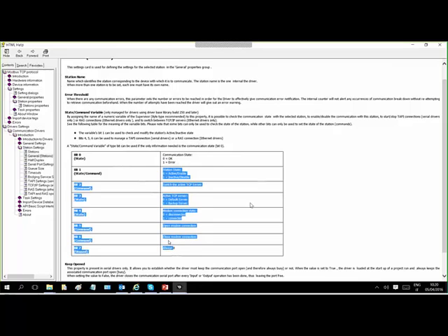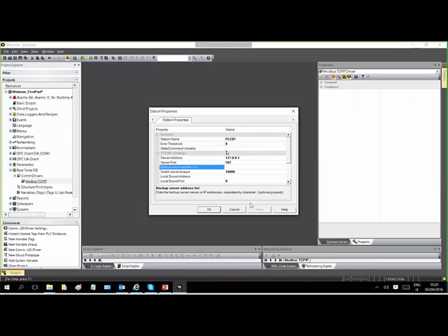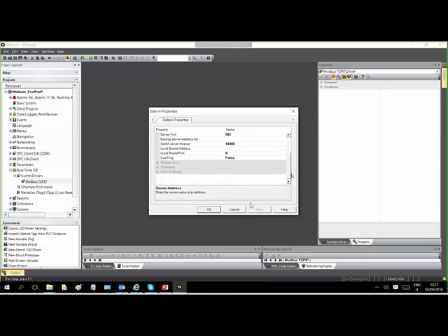Then there is other interesting information. Enable or disable the driver dynamically through logic, through a variable. Switch between, if you apply redundancy at the driver level, because here you can add a second IP address. So you can apply redundancy at different levels, in different contexts. Here, looking at the communication driver in the station, adding two IP addresses. So the IP addresses and the other settings are here.